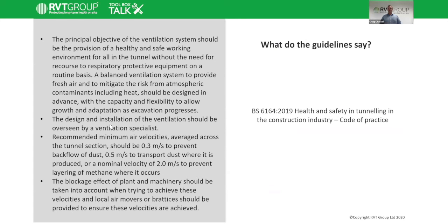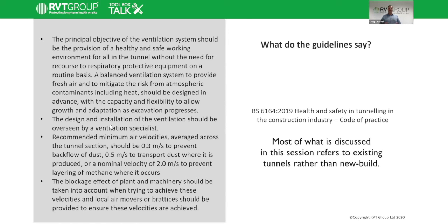When we are considering a ventilation solution, particularly for the tunnel environment, what are we guided by? What do the guidelines say? So we work to the BS 6164, which is a code of practice which covers tunnel construction work, and it has recently been significantly updated, particularly with major changes to the expectations around ventilation and air quality control. I feel it's important to point out that most of what we've discussed today is around existing tunnels rather than new build, but we should still consider where and how this standard applies to existing tunnels.